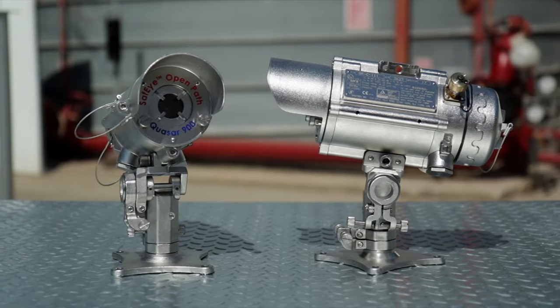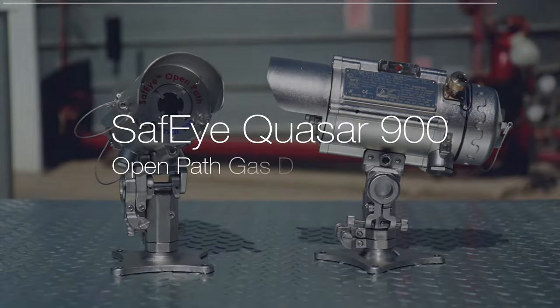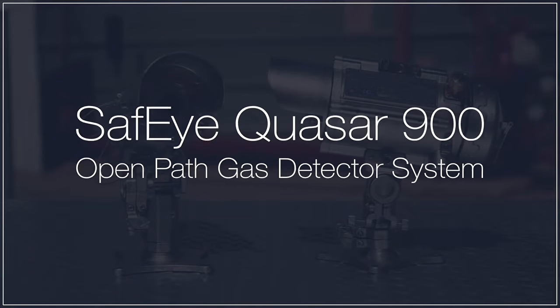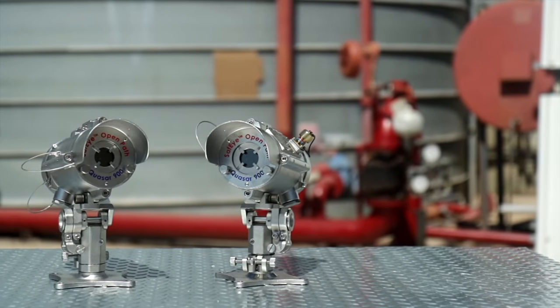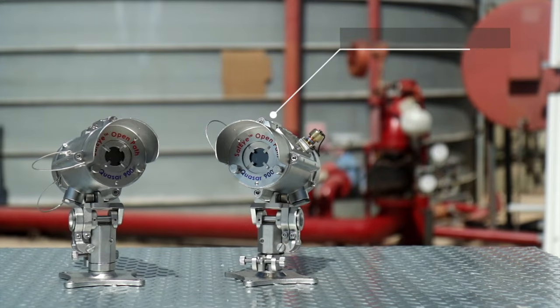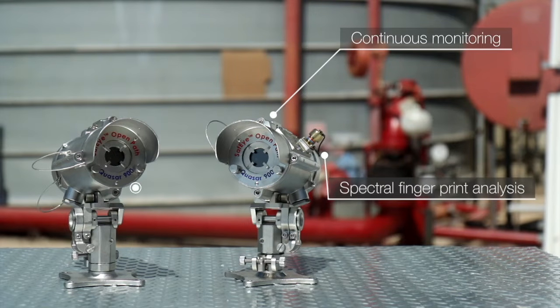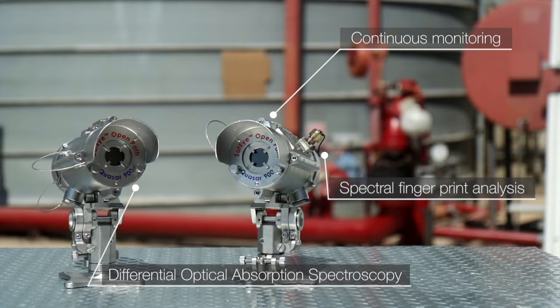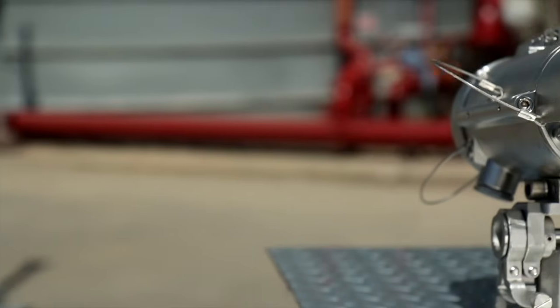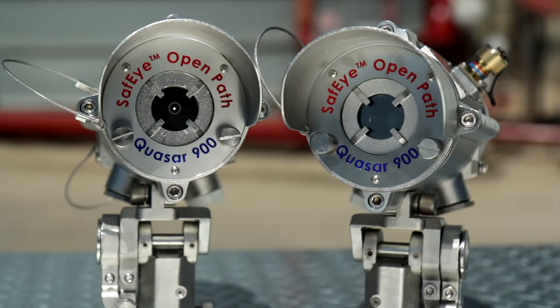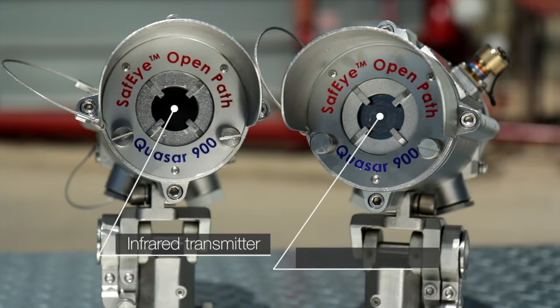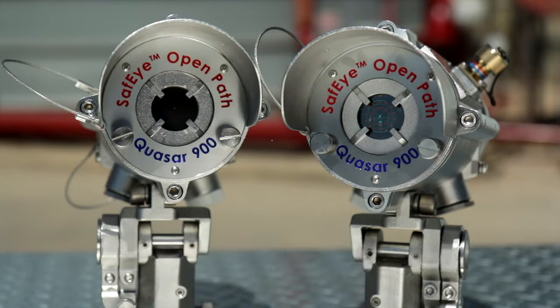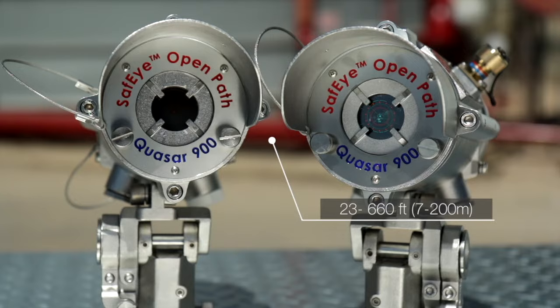This video demonstrates best practices for installing, aligning, and testing the Spectrex Quasar 900 Open Path Gas Detection System. The Quasar 900 is an open path gas leak detection system which provides continuous monitoring for combustible hydrocarbon gases. It employs optical analysis of the atmosphere to detect the presence of combustible gases at an explosive level. The Quasar 900 consists of a xenon flash infrared transmitter and infrared receiver, separated over a line of sight from a minimum of 23 feet up to a maximum of 660 feet.